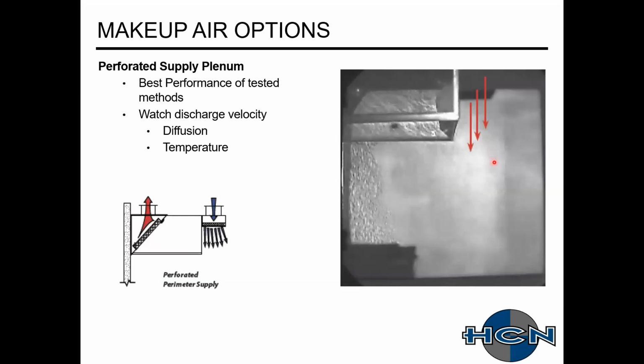What's standard now for most manufacturers is a perforated supply plenum. Basically, when you're designing these types of systems, what you really want to watch is the velocity of that air coming down. We want to make sure we're anywhere from, I think, 140 to 150 feet per minute max right here, so that by the time it gets to the edge of this hood, you're right around 90 feet per minute. And then that air is kind of pushing down a little bit and then gets sucked back into the space. There's a lot of CFD analysis in different reports. I didn't include them here because they're more manufacturer reports, not based on ASHRAE's research project testing.